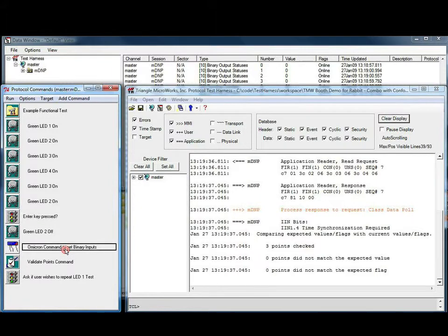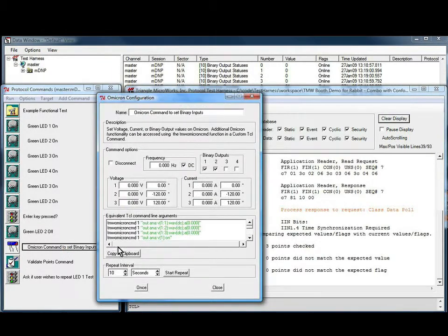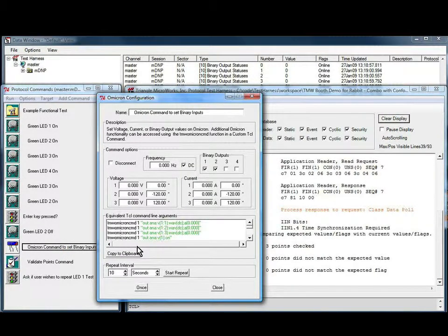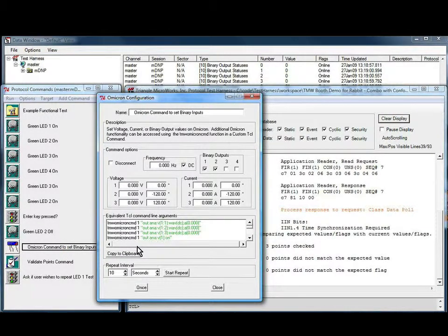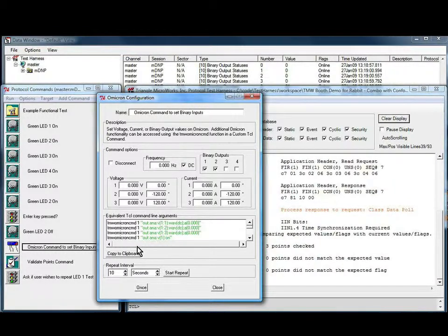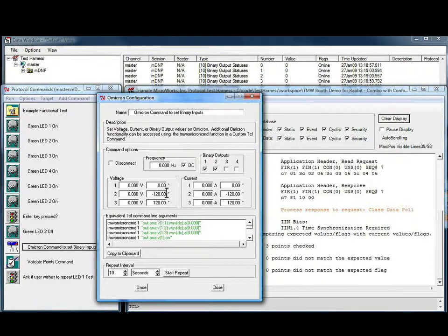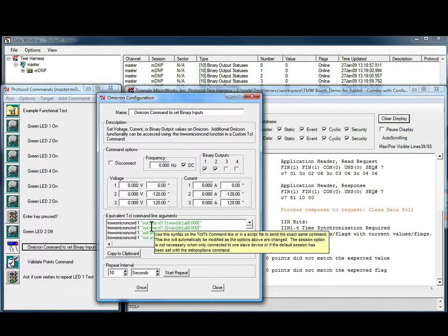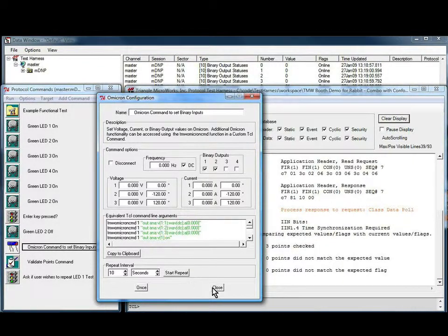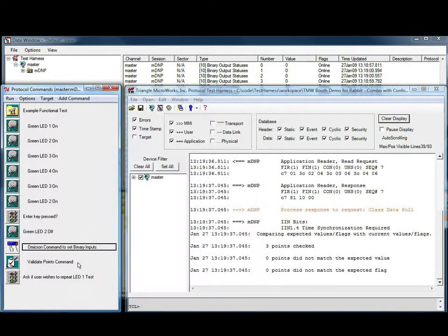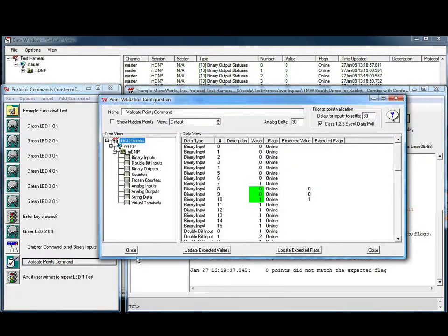This test also uses an Omicron command to control an attached Omicron CMC 156. The CMC 156 will set up the required conditions that are connected to inputs on the microprocessor boards. These will then be validated with the validate points command.